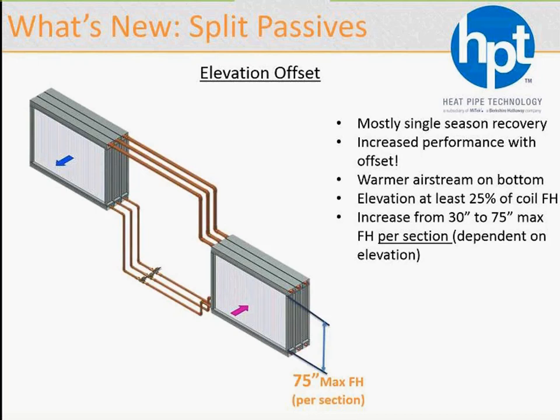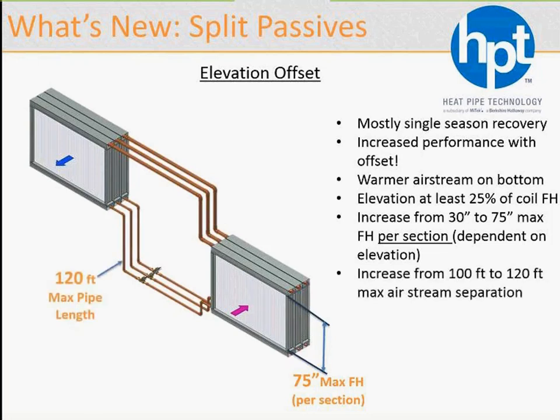Section height, again, similar to the previous product, the HPV, goes from 30 to 75 inches. What does that mean? More area for heat exchange, fewer sections, fewer circuits, better heat transfer, and actually better pricing. There is a significant increase here between supply and exhaust, from 100 to 120 feet. Vertically speaking, that's roughly 10 stories high. So you can actually get this working anywhere from the basement level to the roof of a building. It'll be a single season, but you get the most out of that season.